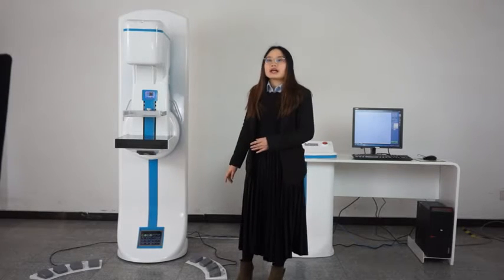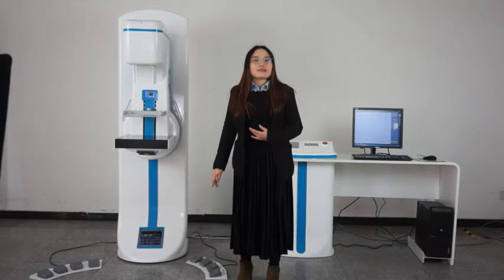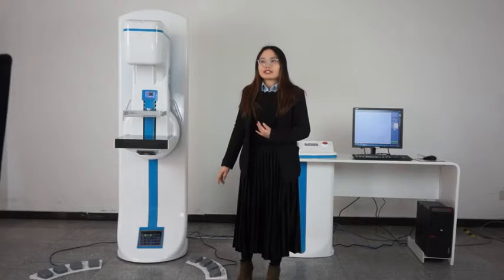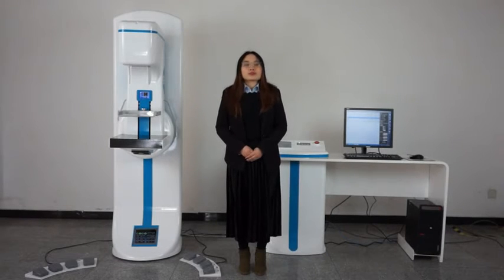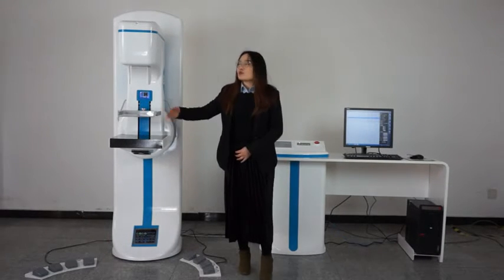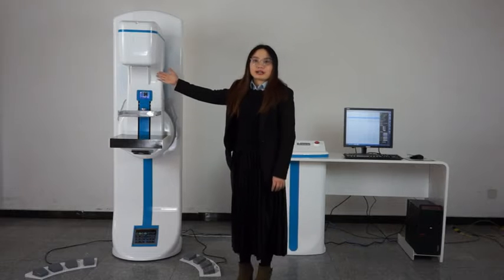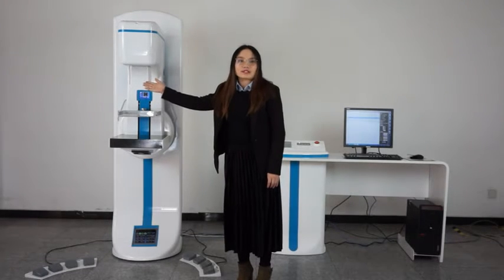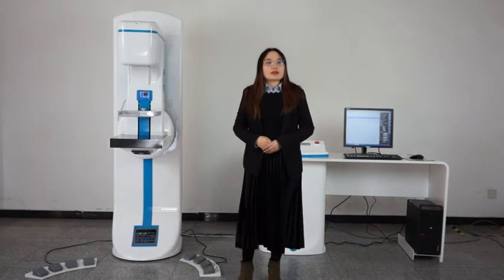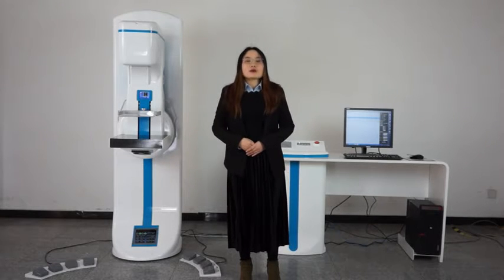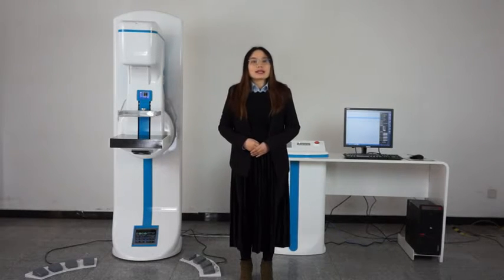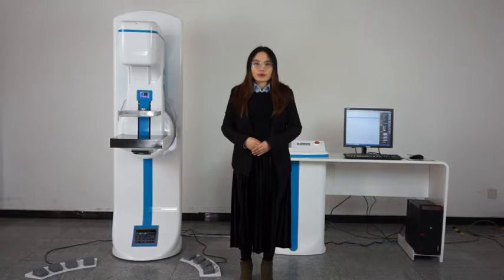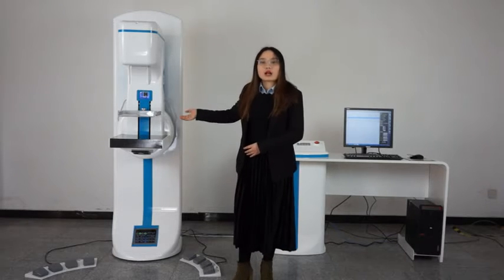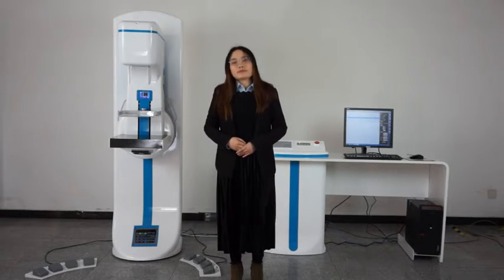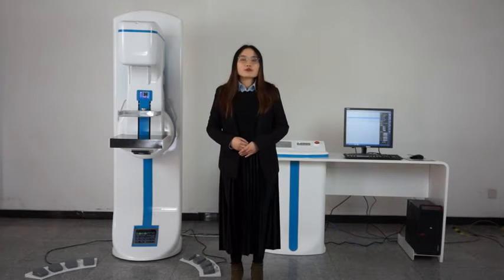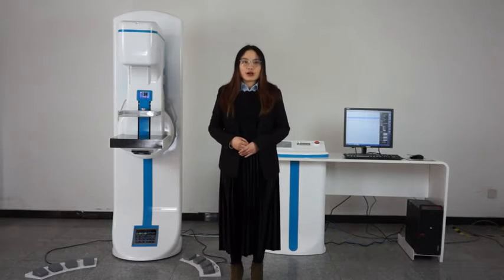It turns out to have a smaller volume, longer life, and lighter weight than the oil tank design. The X-ray tube is from IAE. As a regular importer of IAE, we always have class 1 quality of supply. Dual anode is 0.1 and 0.3 millimeters. Rotation speed is 10,000. Heat capacity is 225 kJ. This allows the whole machine to work for a longer time, especially for a big hospital with busy reception. Of course, there's a Chinese X-ray tube as an option.